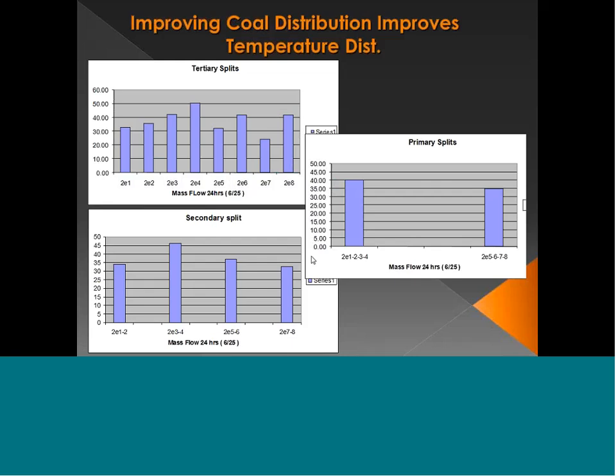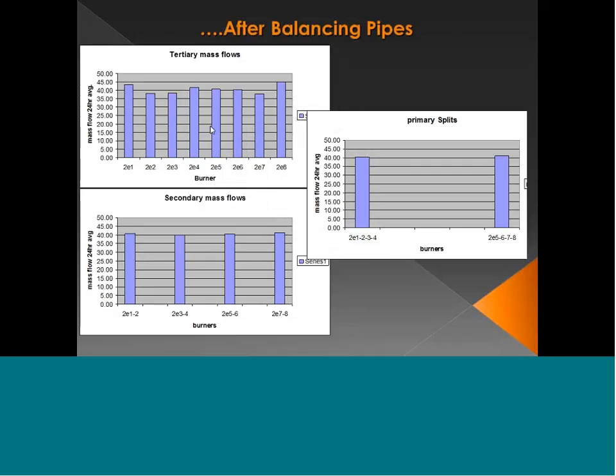This is more T-fired coal data. This was generated by one of our customers, who is very happy that they have some of the best steam temperature distribution they've ever had because they balance flow to their corners. This is the mass flow of coal as summed up to each of the 8 corners on the pulverizer, and that's the as-completed version. So we were able to improve corner-to-corner coal distribution on this T-fired unit, and thus improve steam temperature distribution.